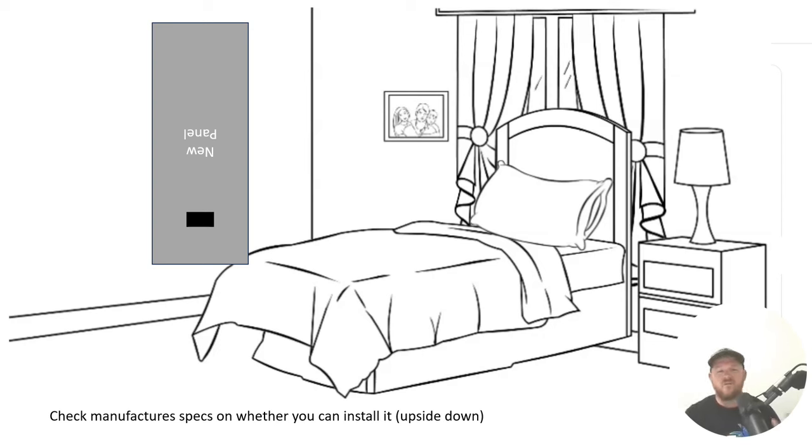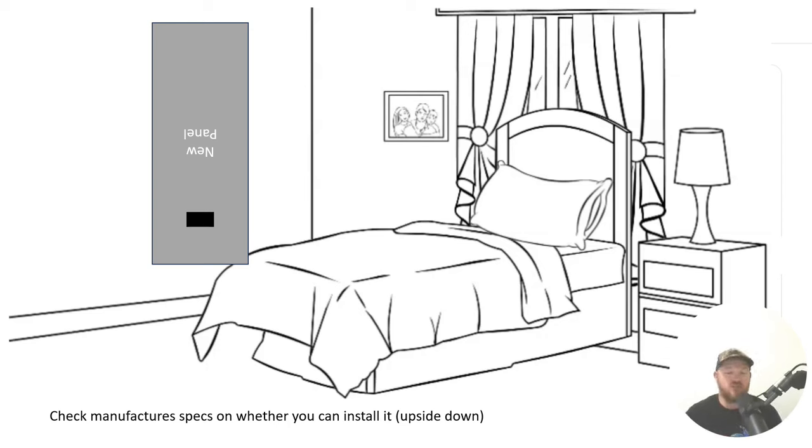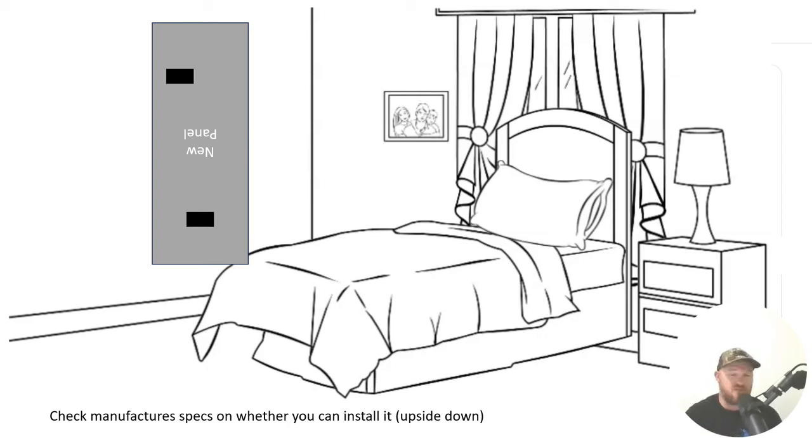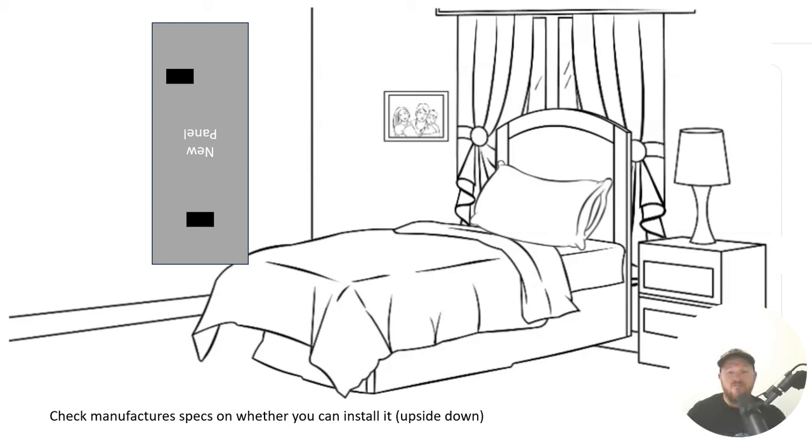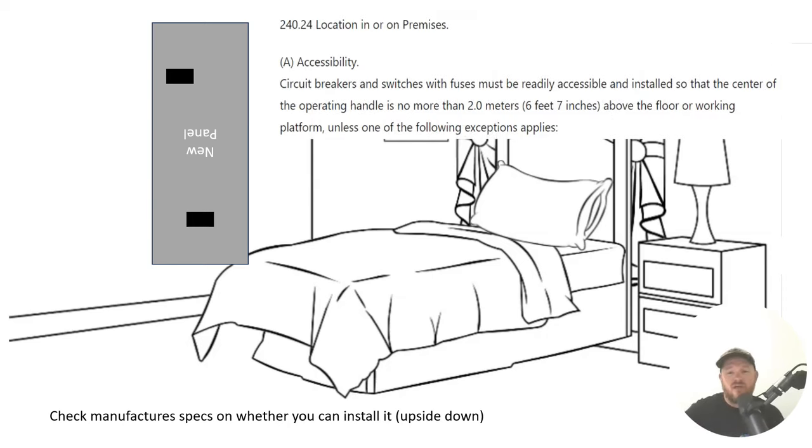I put the word main breaker in today's question on purpose because it's a big misnomer in our industry that the main breaker is not allowed to be higher than 6 foot 7. And that's true. Not allowed to be higher than 6 foot 7. But did you know that every overcurrent device in that panel is not allowed to be over 6 foot 7? As a matter of fact, there are no overcurrent devices that are allowed to be installed above 6 foot 7 unless they're in one of the conditions that are listed below in the code that we're getting ready to cover.